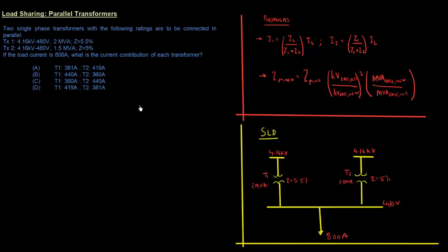Hello and welcome to another video in the Power PE series from Movingelectrons.com. Our topic for today is parallel transformers. We've been given two single-phase transformers with the following ratings to be connected in parallel. They have the same voltage ratio — 4.16 kV primary and 480 V secondary. One is a 2 MVA transformer with 5.5% impedance, the other is 1.5 MVA with 5% impedance. The load current is 800 amps. We need to find the current contribution of each transformer.